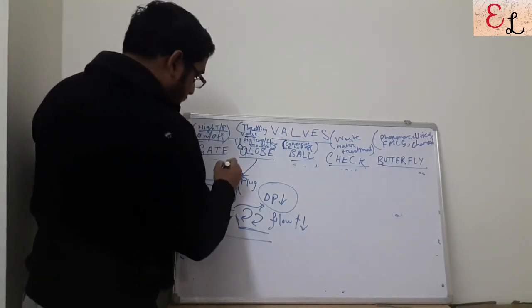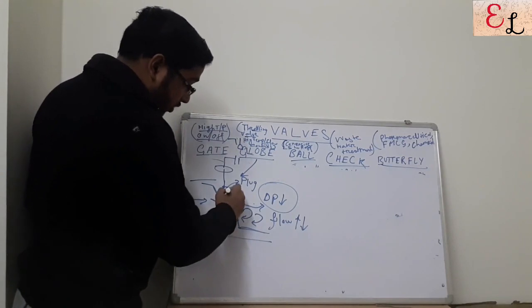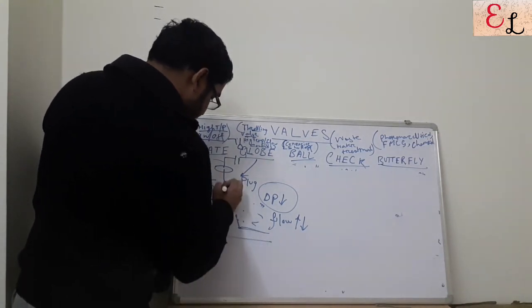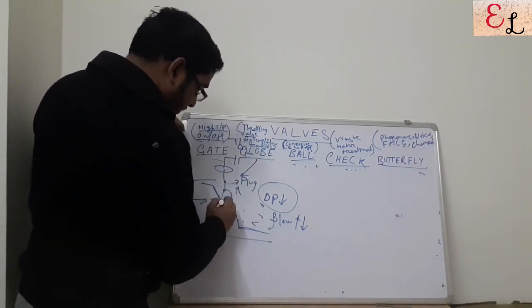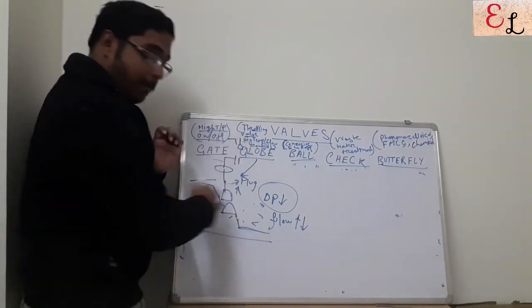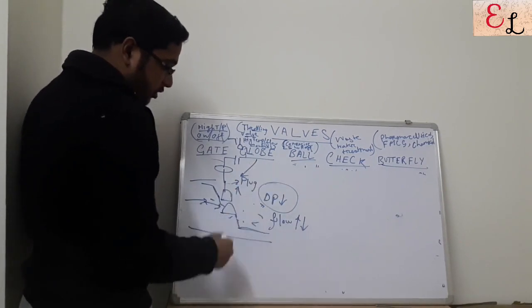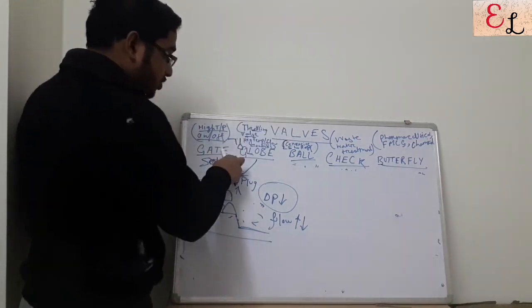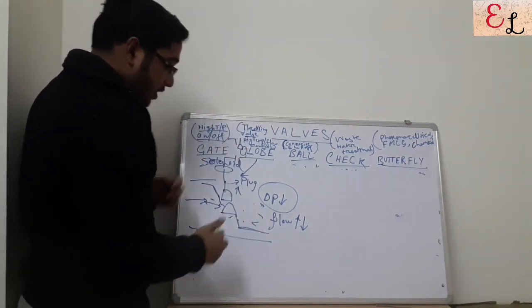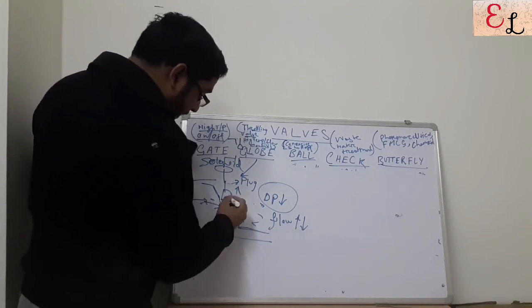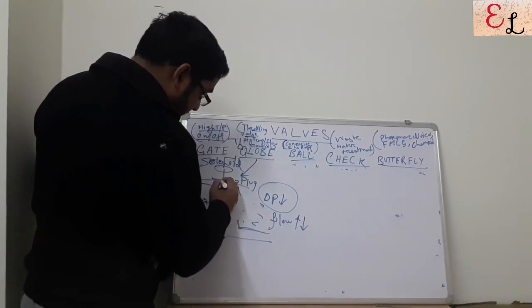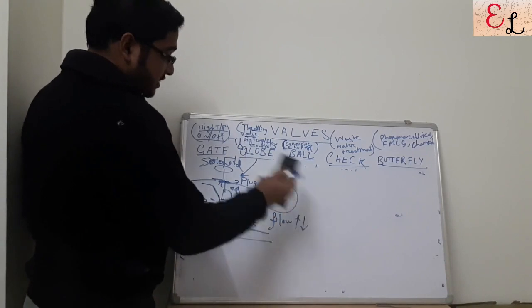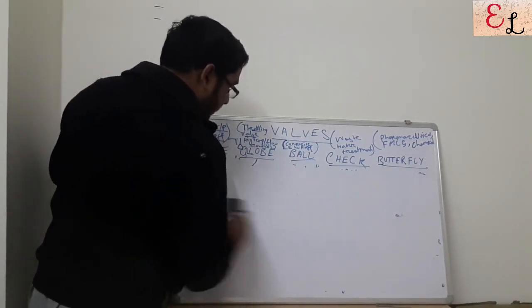Talking about the solenoid control: the solenoid valve is connected to a voltage source. As soon as the voltage is off, the plug fits into the gap — this is complete shutoff and it does not let liquid flow. This is how a solenoid globe valve operates — it runs on voltage, and whenever voltage is zero, it completely shuts off. Moreover, the fluid flows into multiple areas of the plug and the sealing disc — it has multiple entry points and can attack the sealing disc, so the sealing is prone to leakages, especially if it is a pulsive fluid.